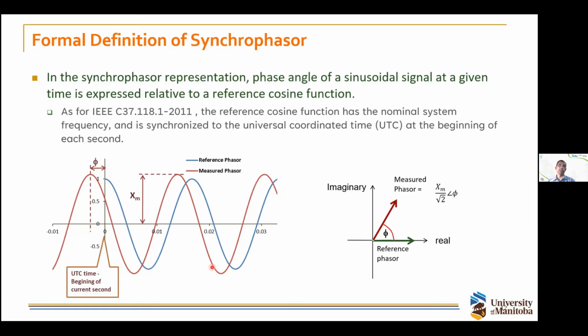For example, this red colored measured phasor has its peak occurring at this point, so there is some time difference between the peaks. That time difference can be converted into a phase angle difference based on the frequency. This phase angle, measured with respect to the blue reference phasor, we call a synchrophasor.